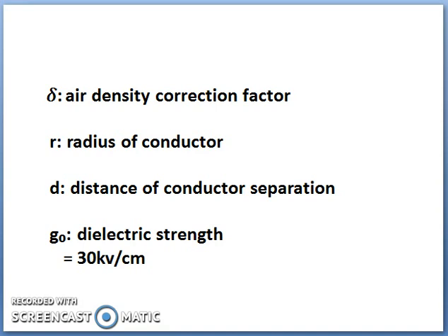The atmospheric conditions change — the temperature may vary and the pressure may vary. So you need to take a correction into account, which is taken care of by delta. The air density correction factor depends on pressure and temperature, and delta is given by 3.92B divided by (273 + T), where B is the barometric pressure in centimetres of mercury and T is the temperature in degrees centigrade.